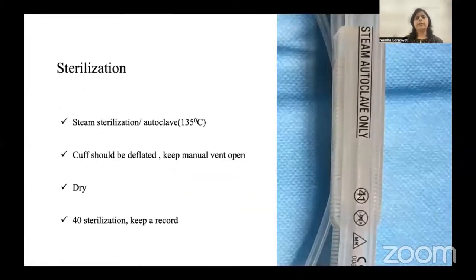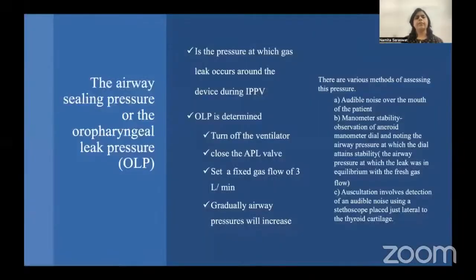Sterilization is done through steam sterilization, that is autoclave at 135 degrees centigrade. The cuff should be deflated and the manual vent kept open. That red colored vent which I showed you previously should be opened. Before putting the device, it should be dried. Maximum 40 sterilizations are allowed, and for that you have to keep a track.